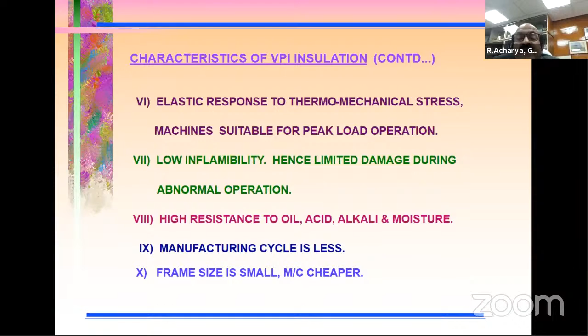Unlike other kinds of insulation systems where individual bars are placed, here it is supposed not to fail at all. It is fit and forget. It can, in fact, be used as a submerged one. You can water jet it also, and it can operate. That's the kind of advantage of a total impregnation system. You can see here, the IEC standards that I have referred to permit almost 2% of tan delta at 0.2. It actually gets almost 0.7, one third of the total permissible value. This is one advantage of a total VPI insulation system.